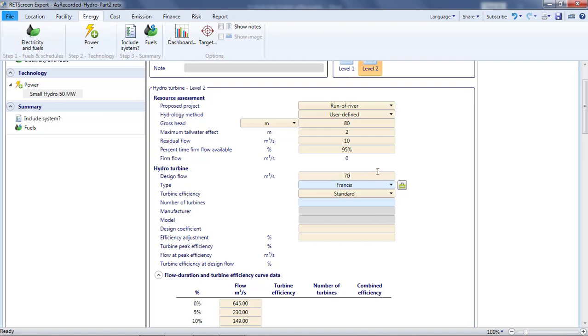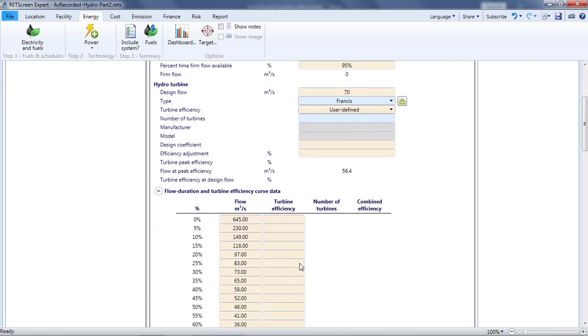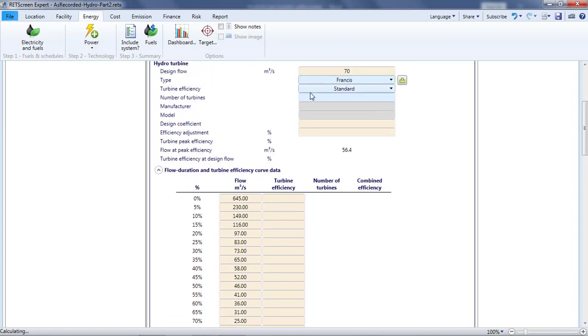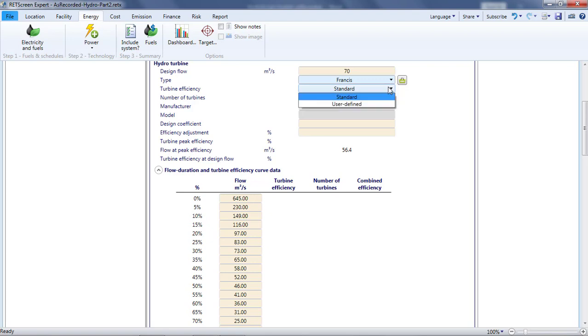If I knew the efficiency of my turbine as a function of flow rate, I'd select User Defined for Turbine Efficiency and enter the data from the curve in the table below. Note that each entry in the turbine efficiency curve is for the percentage of design flow for the individual turbine, as indicated at the left of the table. Ignore the flow that appears in the column between the two. It is completely unrelated to the specification of the turbine efficiency curve. I don't have a turbine efficiency curve. Fortunately, RETScreen can propose a typical curve based on the type of turbine, the design flow, and two adjustment parameters. To use this typical efficiency, I select Standard for the turbine efficiency.